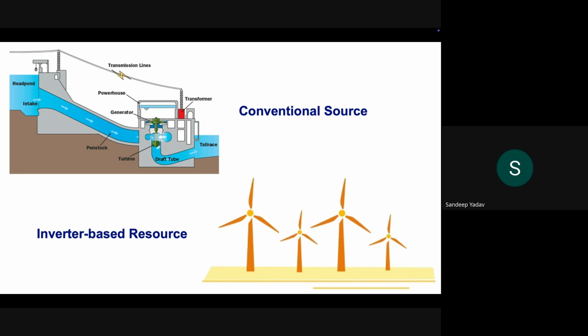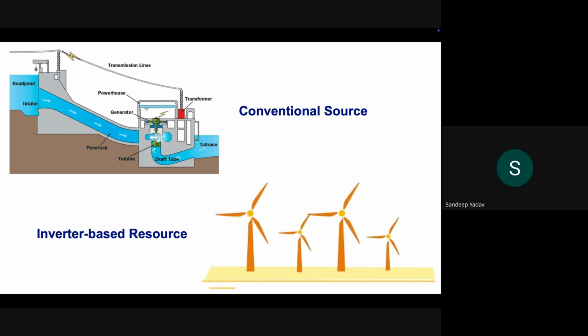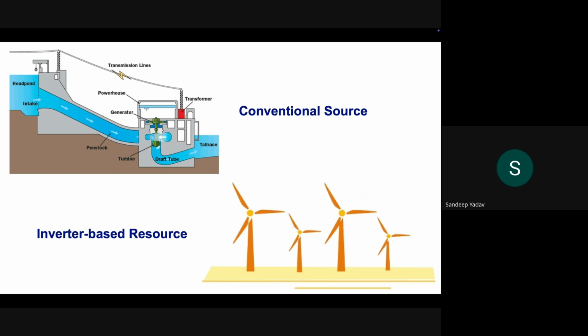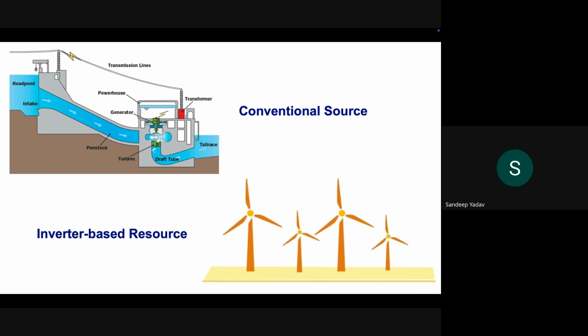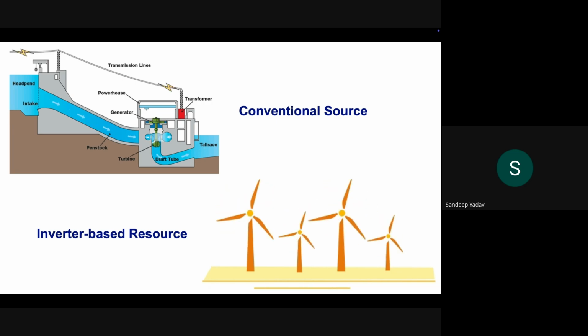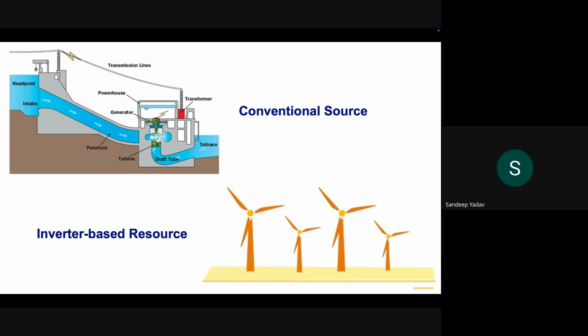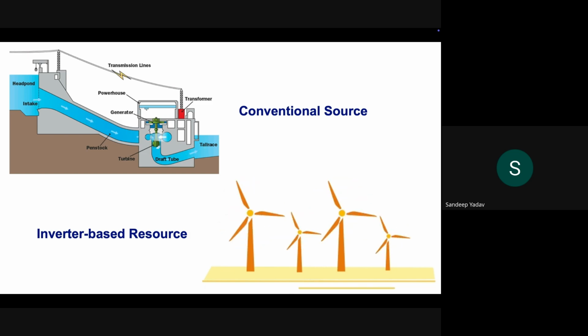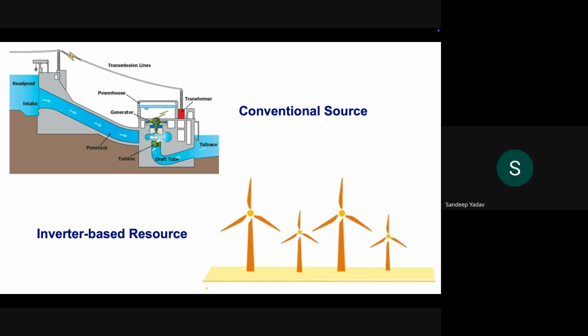However, as we are moving towards more and more converter-based resources, also known as IBR, inverter-based resources, these machines do not have a large rotating mass. They are mostly in the form of power semiconductors, and the electromagnetics is totally decoupled. The load is totally decoupled from the generation. The dynamics that we have been seeing, with energy coming from one side to the other and coupled through an electromagnetic medium, is not the case with inverter-based resources. So both in steady state and in dynamic state, they are very different from the conventional sources.